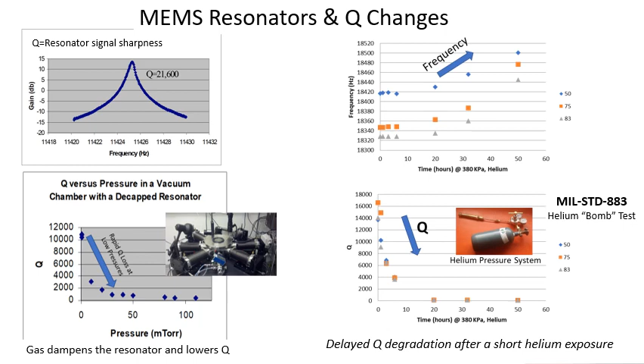It's really been interesting. You can just have a short amount of helium pressure exposure, say a very short helium bomb test. You can measure the Q, it looks pretty good, but then over time the helium will seep in through different seals or crevices and gradually decrease the Q after just a short helium exposure. So you might think initially, hey, the part looks good in helium, but then over time your Q value will decrease.